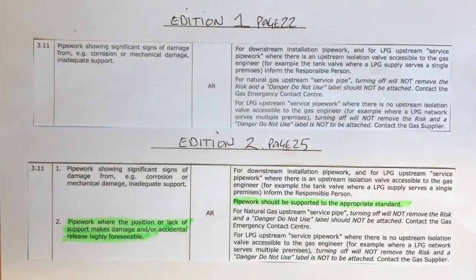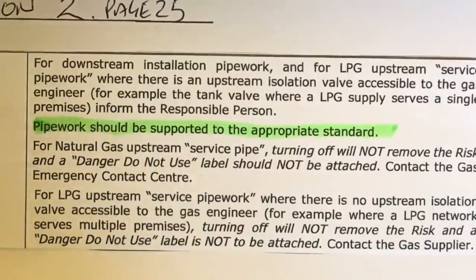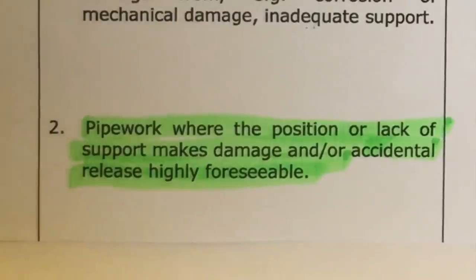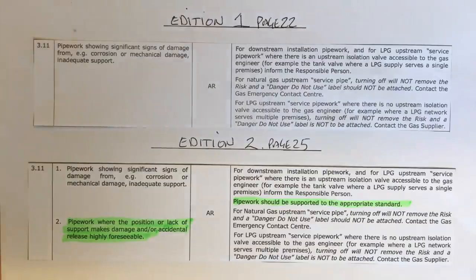The next change is table reference 3.11, where the guidance notes have been revised — highlighted in green. The main addition states that pipework where the position or lack of supports makes damage and/or accidental release highly foreseeable will be classed as 'at risk'. Pipework should be supported to the appropriate standards.